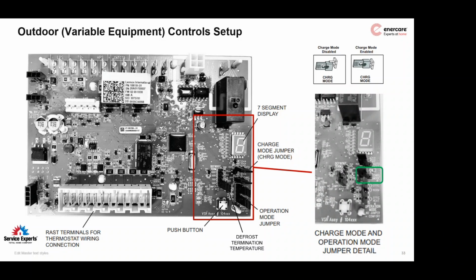Okay, I see. Now, I guess my question then is, if there is an S40 installed with this variable outdoor unit, then we can ignore it. You don't need this charge jumper. You don't need to do anything with this charge jumper. Then the S40 can handle it, run it at max, and then it'll run the indoor. Yeah. So with the S40 version, you can go inside of the S40 and force it to maximum through your installer settings or your advanced settings. Or if you're working outside and you want to jump this jumper, the entire communicating system will recognize that you've done that and will force everything to 100% immediately.